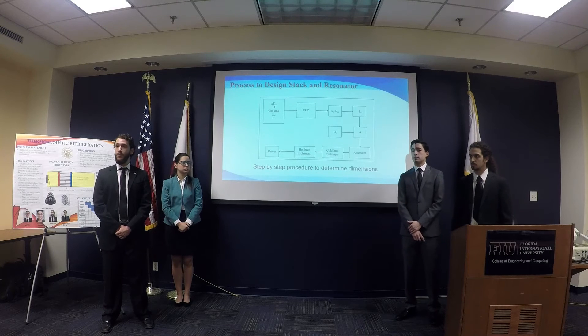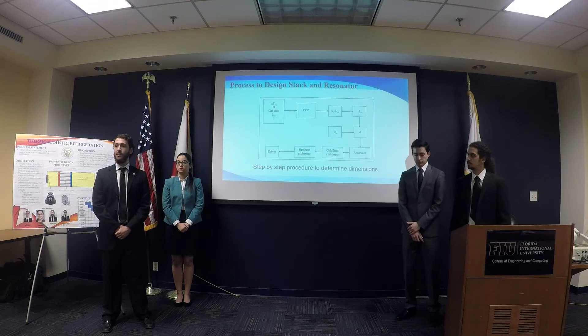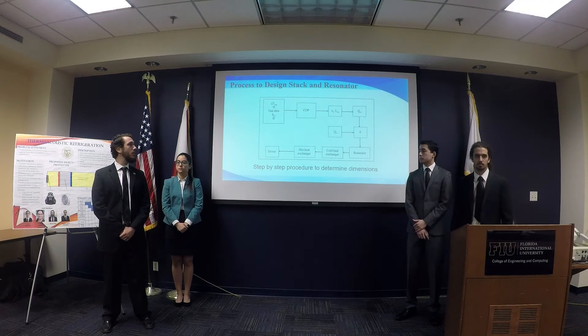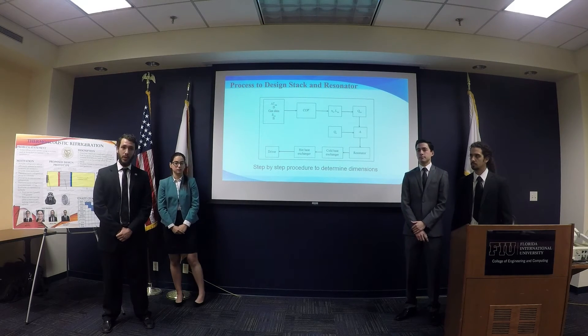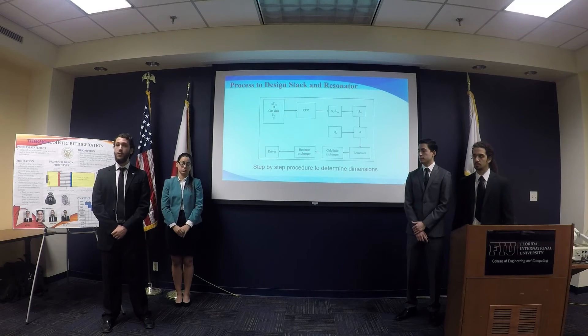As you can see in the figure, it's a simple step-by-step design process. You begin by selecting your gas, your desired temperature range, and a required cooling power. The next step is to optimize these parameters to raise the COP. After that, you determine the normalized center position of the stack and the normalized length of the stack. Using those two variables, you calculate the normalized cooling power, and using your required cooling power, you determine the cross-sectional area, which is the same as the inner cross-sectional area of the resonator.